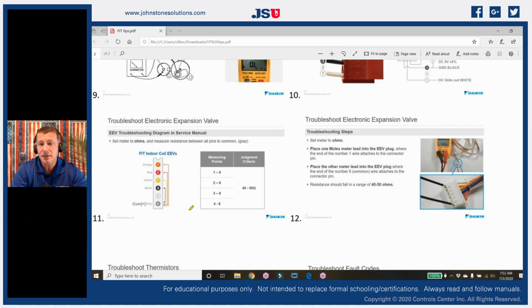So we can check the resistance on those solenoids, because a lot of people will condemn an electronic expansion valve in the field without ever even checking the solenoid. And so the solenoid is just 4 coils, all going back to common. So like ours, it's on a 6-pin connector. Well, here's our 6-pin connector right here. And we're only using 5 of the wires.